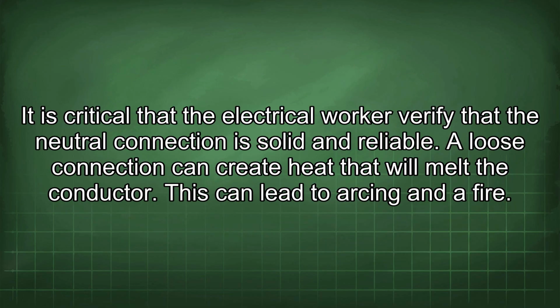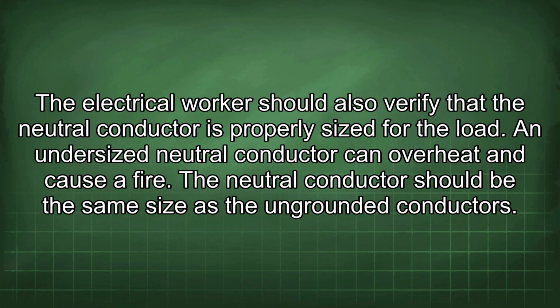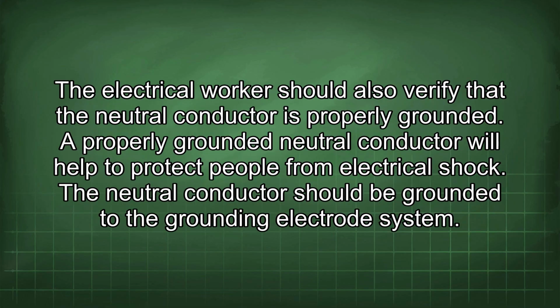It is critical that the electrical worker verify that the neutral connection is solid and reliable. A loose connection can create heat that will melt the conductor. This can lead to arcing and a fire. The electrical worker should also verify that the neutral conductor is properly sized for the load. An undersized neutral conductor can overheat and cause a fire. The neutral conductor should be the same size as the ungrounded conductors. The electrical worker should also verify that the neutral conductor is properly grounded. A properly grounded neutral conductor will help to protect people from electrical shock.